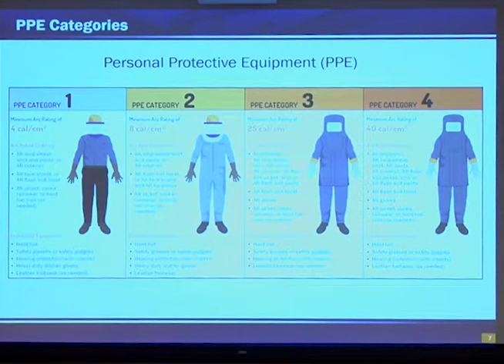In TxDOT, we only have to worry about the first 2 categories, Category 1 and Category 2. Sorry, ladies and gentlemen, but the spacesuits in Categories 3 and 4 will not make it into our fall fashion this year. So for PPE Category 1, its incident energy begins at 1.2 calories per centimeter squared to 4 calories per centimeter squared. So the ARC-rated clothing we need is long sleeve shirt, ARC-rated pants, ARC-rated coveralls, face shield, flash suit hood, jacket, parka, hard hat, safety glasses and goggles. We need to wear hearing protection with inserts, leather gloves, and electrically rated safety boots.